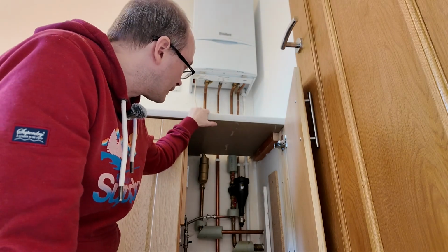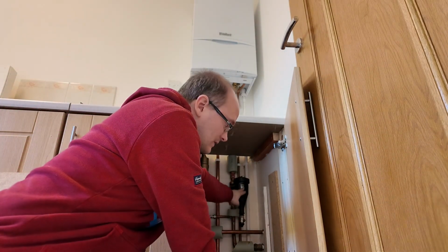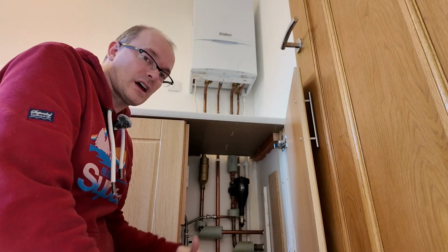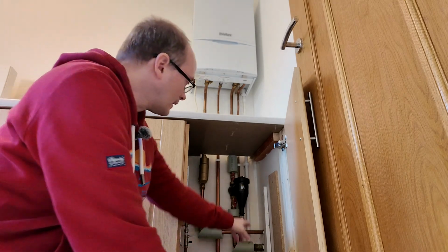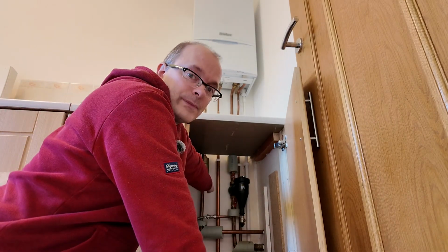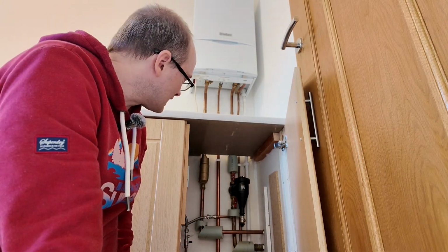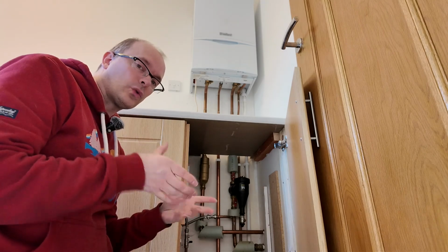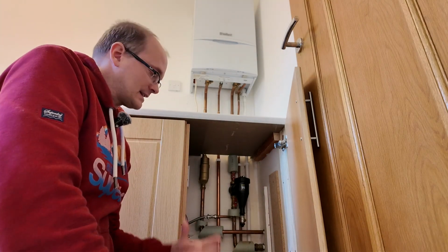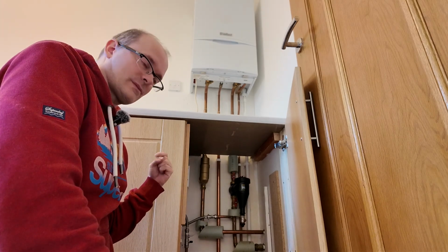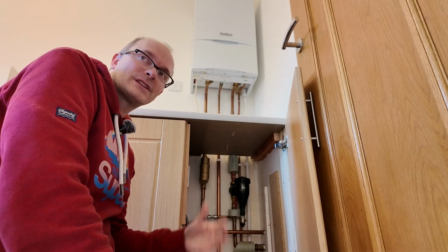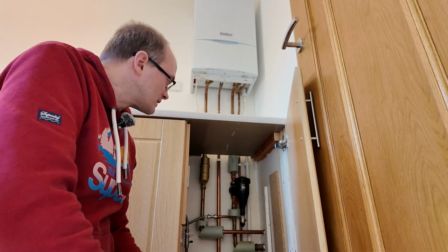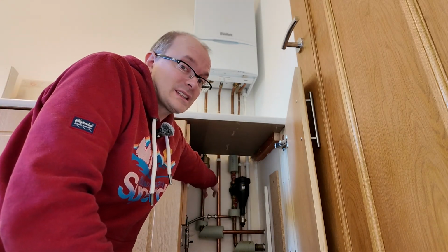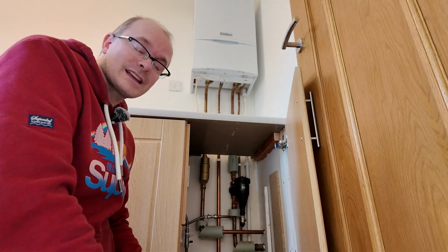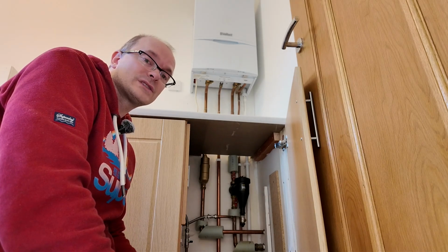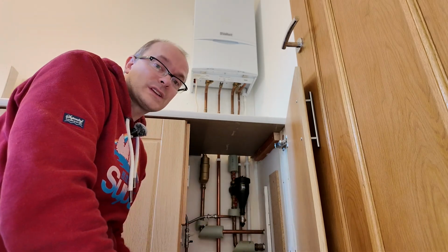boiler worktop. This is the magnetic filter. That's used for keeping any iron oxide sludge under control before it goes into the return line, before it goes into the boiler. And then on the flow line here, we've got what's known as a deaerator. This is used for removing all the microbubbles from the heating medium. And in removing the microbubbles, you reduce the rate of corrosion of the steel radiators from the inside. So this was fitted about 7 years after the boiler was fitted, and it has been remarkable in terms of reducing the amount of work that the magnetic filter has had to do since then.